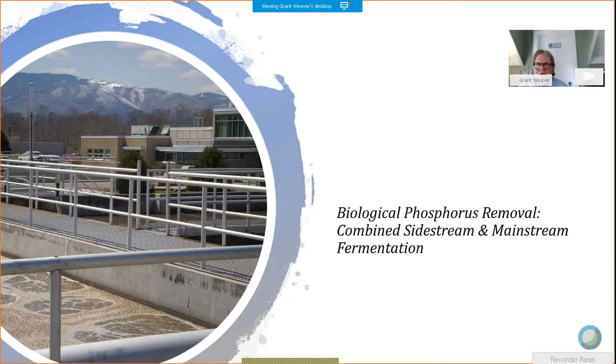Thank you for that. I'm going to address a plant that's actually managing the primary clarifiers to blow the solids from the primary clarifiers into their aeration basins, in part because of that concern. But it's more than that. Volatile fatty acids are formed in the septic conditions. They will go into the water, okay? So the short answer to the question is no, you're really not. Volatile fatty acids will be in the water column and will flow through in the water column leaving the primary clarifiers. And they'll be available to whatever bacteria wants to eat them, whether they're denitrifying bacteria or phosphorus bacteria.